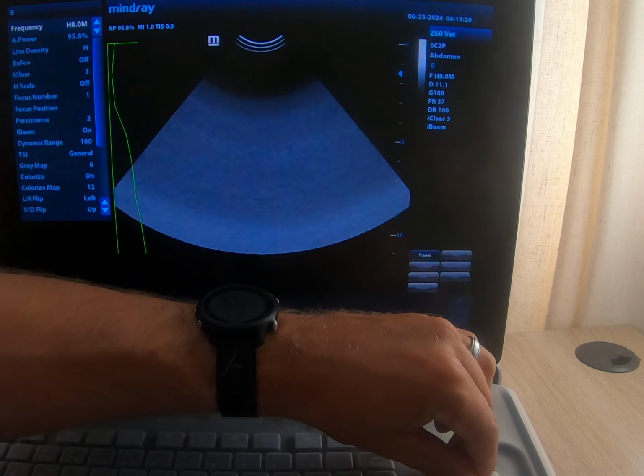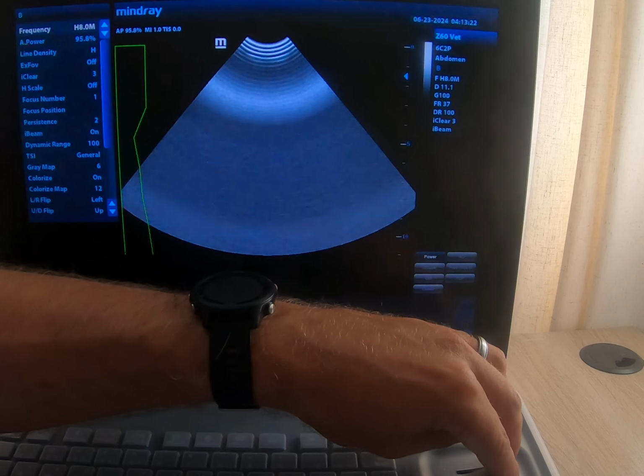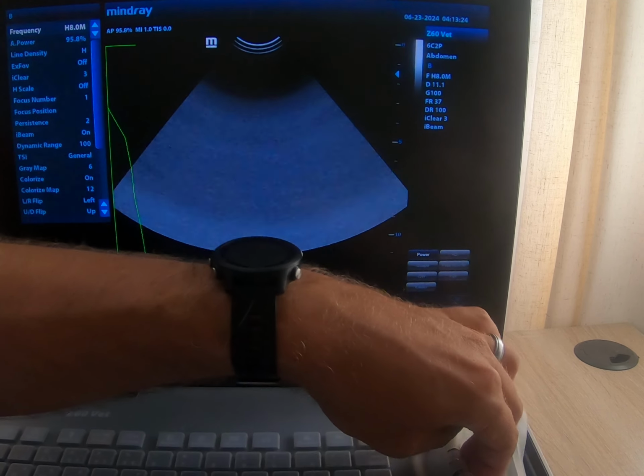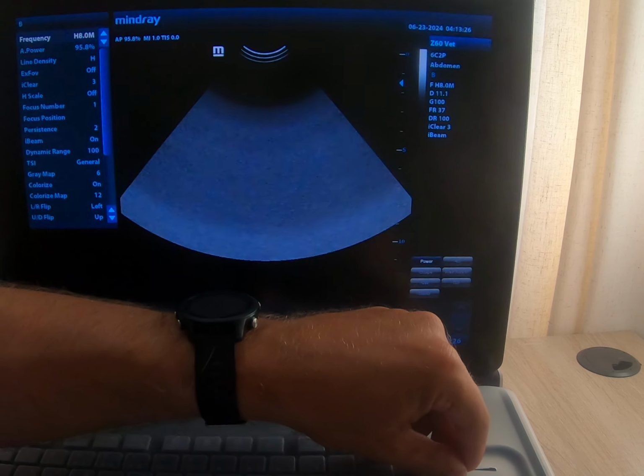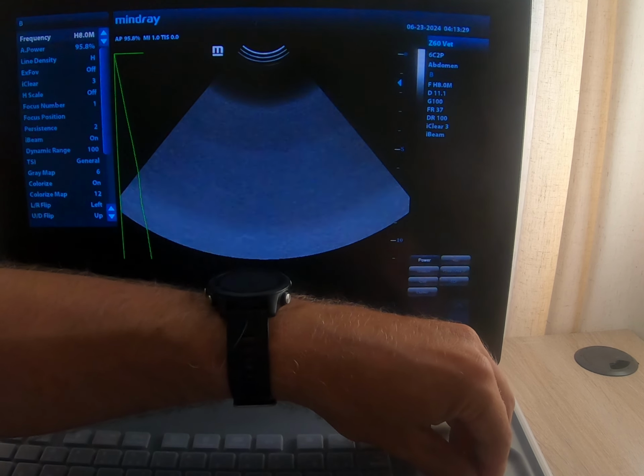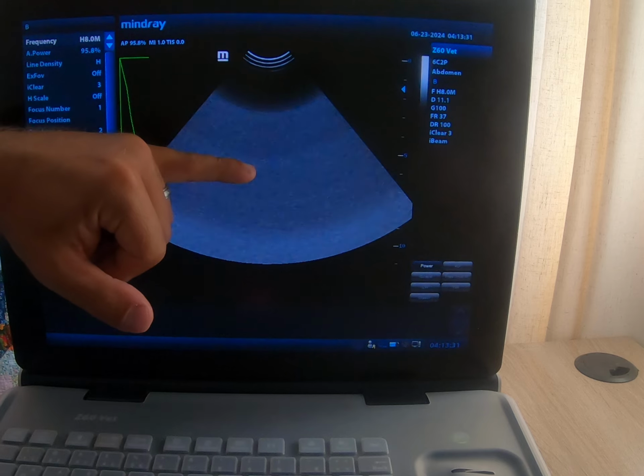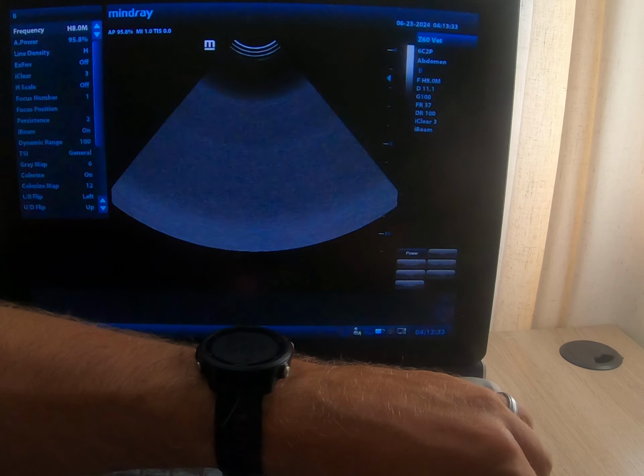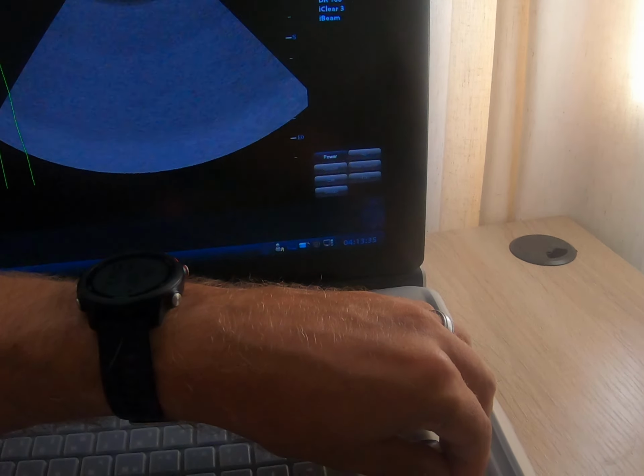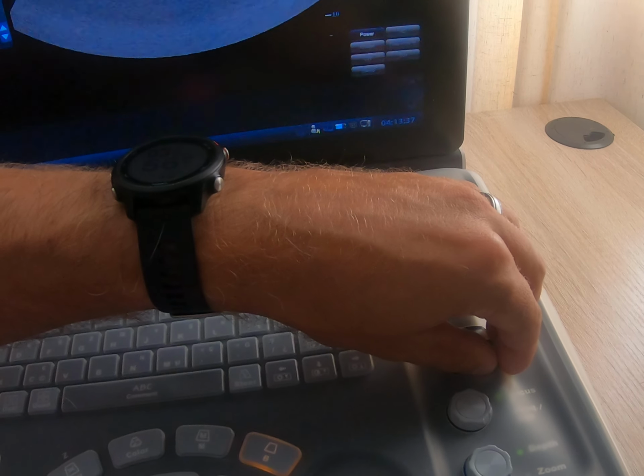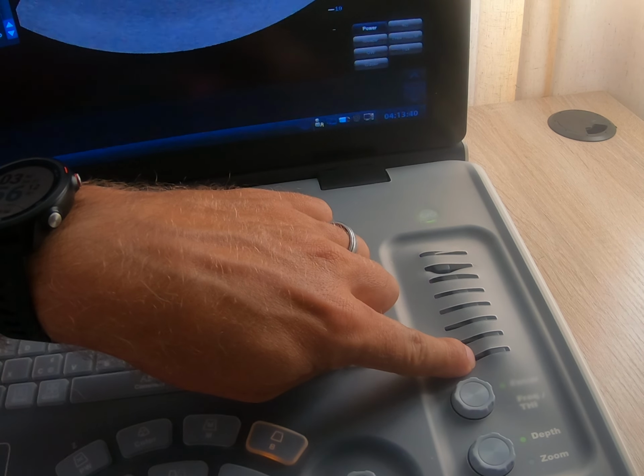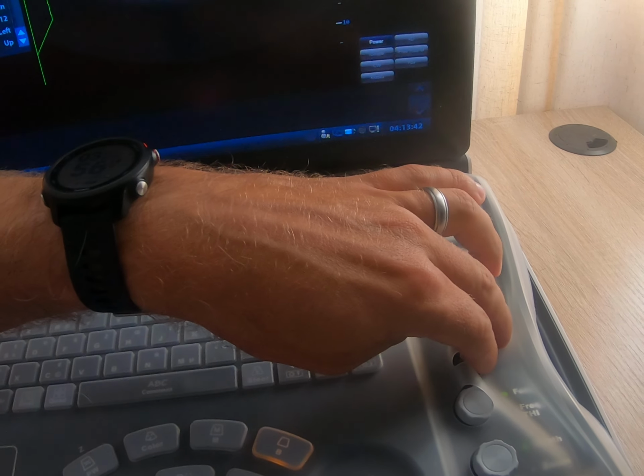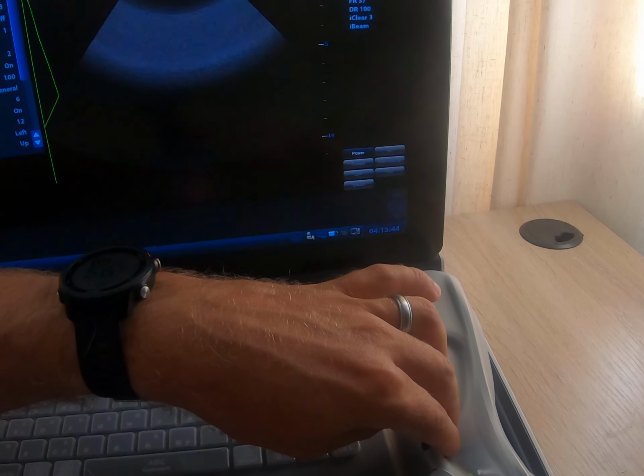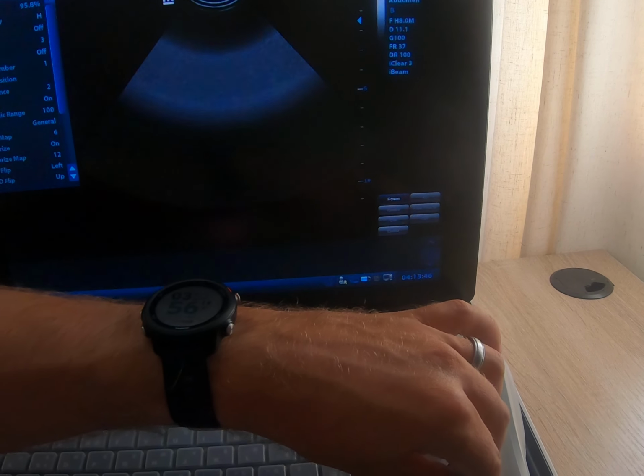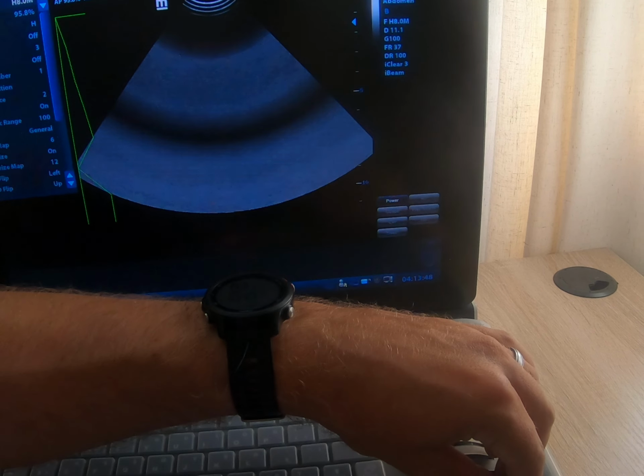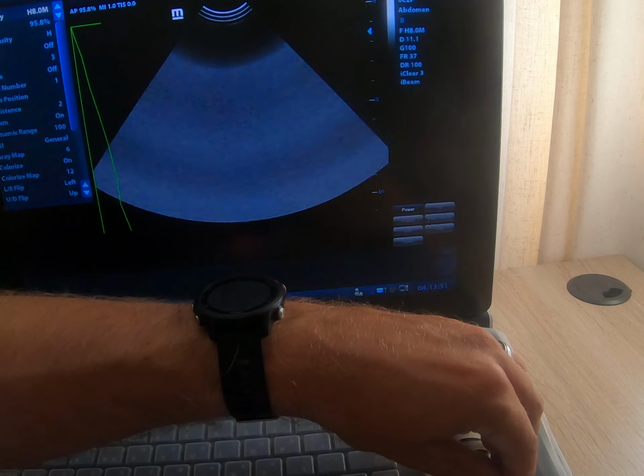So you see darker, increase the gain, brighter. So just in this one area right here, each level of this time gain compensation will correspond to a different depth on here. So if I wanted to change all the way down at the bottom of these controls, kind of all the way down here, and I change that gain, you can see how the bottom of the screen went really dark there. And if I increase the gain, it gets really bright again.